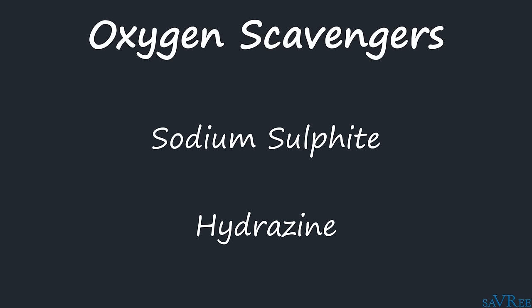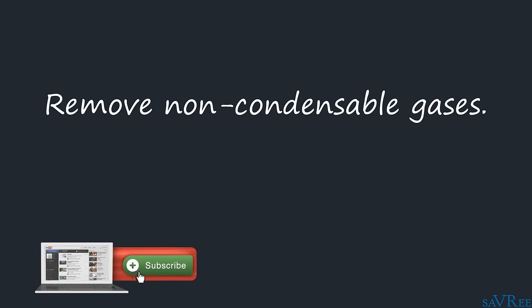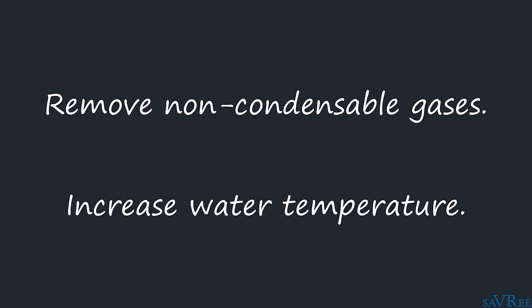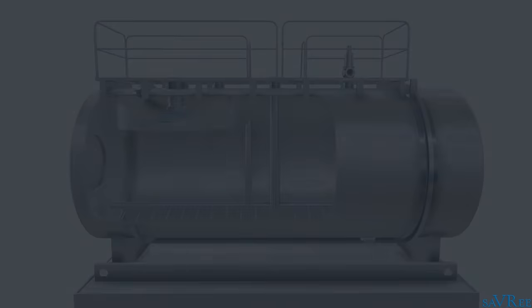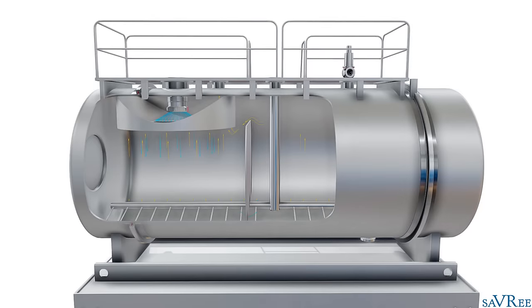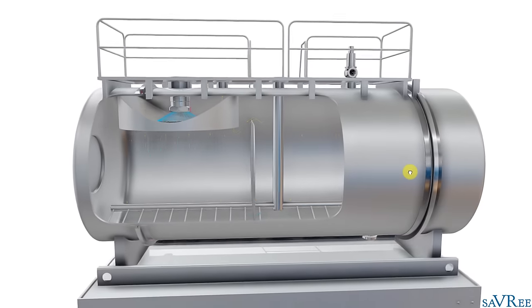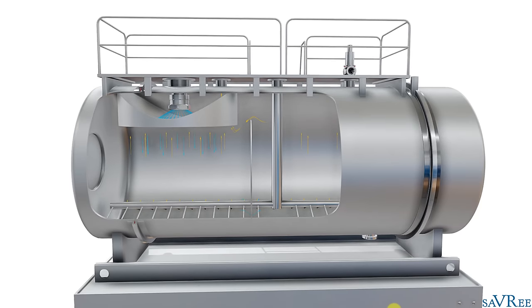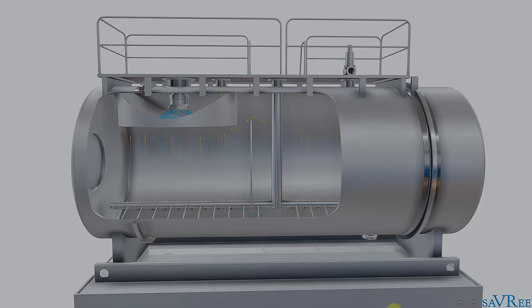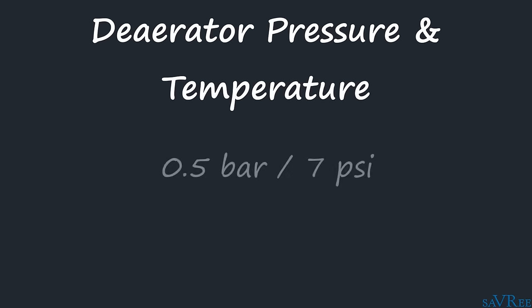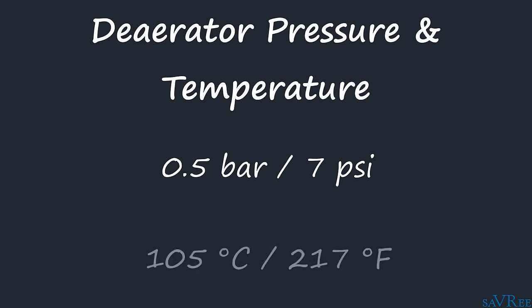Let's now have a look at our first deaerator design. I'll explain exactly how it works, how we can get those non-condensable gases out of the boiler feed water, and how at the same time we can increase the water's temperature so we don't thermal shock the boiler. Here's our first 3D model of a deaerator — I'll do a little spin so you can have a look at it. You can see it's horizontally orientated and is actually a pressure vessel, although the pressure is quite low — about 0.5 bar, which is about 7 psi. The temperature of the deaerator should be approximately 105 degrees Celsius, or 217 degrees Fahrenheit. Pressures and temperatures do vary based upon the deaerator design.